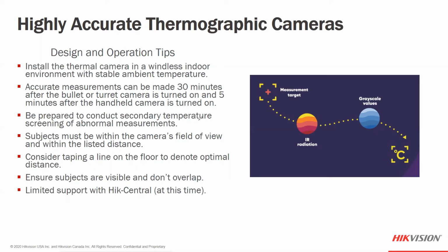The subject does have to be within the correct field of view. They shouldn't be making a temperature measurement 10 feet away when the detection range for accuracy level is between 3 and 5 feet. So you do need to make sure that maybe you tape something on the ground, or give them stanchions to walk through or whatnot. We've seen a lot of our videos actually contain that kind of line or cue for them to walk through. And we do want to make sure that people don't overlap and hide faces behind other faces. It will affect the accuracy level, as one head could be behind another head, and then they need to slow down. So the idea is to definitely have a good line of sight.